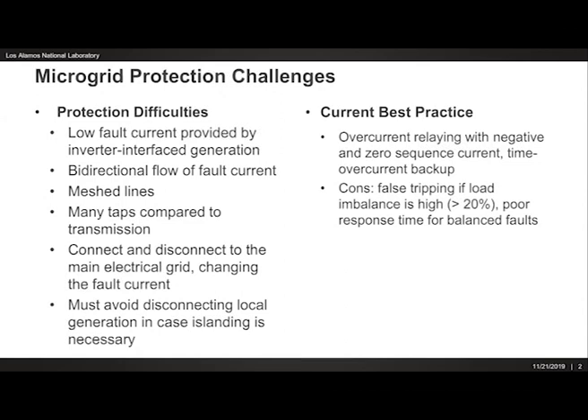Traditional distribution system protection relies on overcurrent. It also relies on assuming that the structure of the grid is radial, and microgrids break this. The current industry practice in microgrids is actually kind of embarrassingly simple right now. They generally still rely on overcurrent protection, either zero sequence or negative sequence. This is usually focused on protecting the generation. It also relies on the assumption that all the elements in the microgrid are pretty close to each other. So if protection operates, generally the generation goes offline along with the entire microgrid.